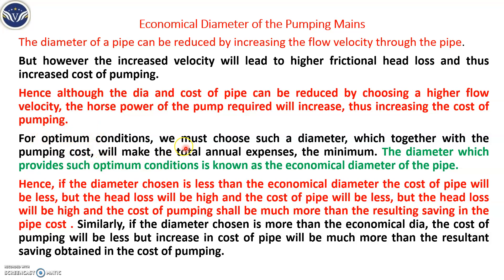The optimum diameter should be one where together the pumping cost and the annual maintenance expenditure are minimum. So the diameter being provided should be at such an optimal condition that you have the least expenditure. That is called the economical diameter of the pipe — the diameter at which pumping cost and total annual expenditure cost is minimum.